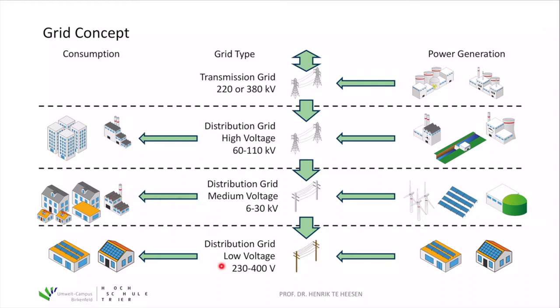Finally, we have the low voltage distribution grid with a voltage of 230 to 400 volts — that's the voltage you know from your wall socket. On the power generation side, PV systems installed on roofs of households, small shops, or schools feed electricity into this low voltage grid. On the consumption side, each building and household takes energy from the low voltage grid, so the distribution within a city is typically done at this voltage level.